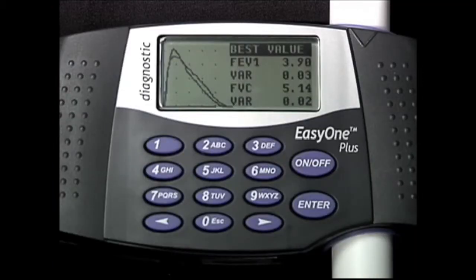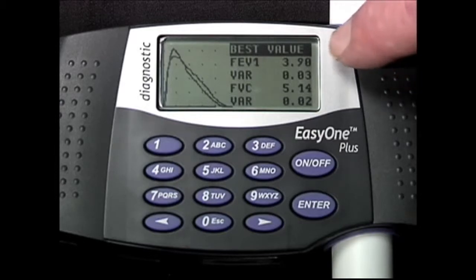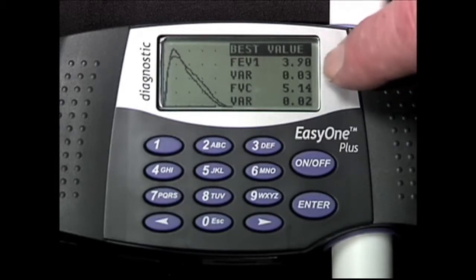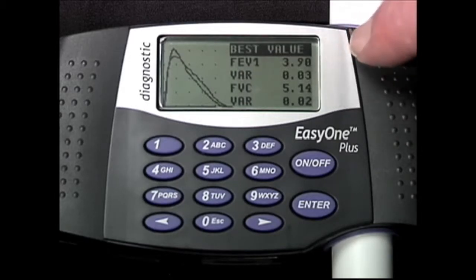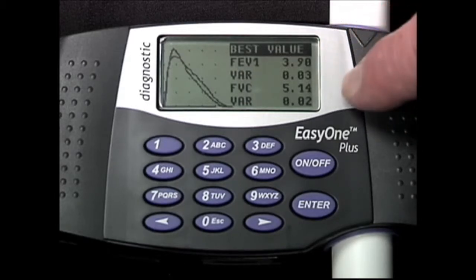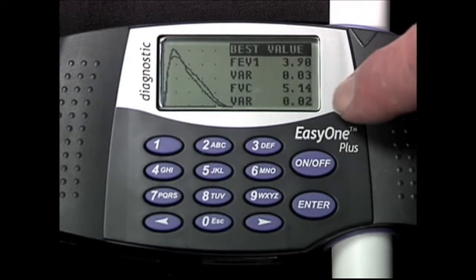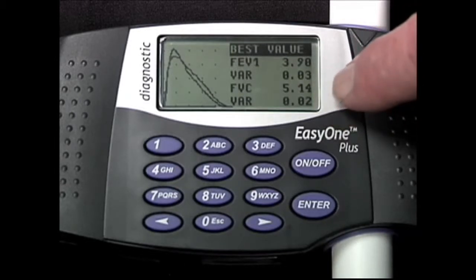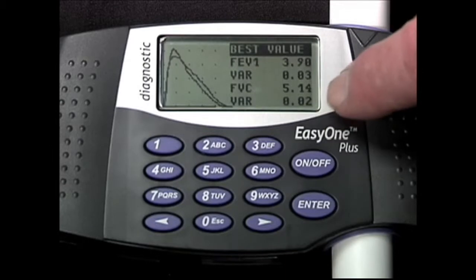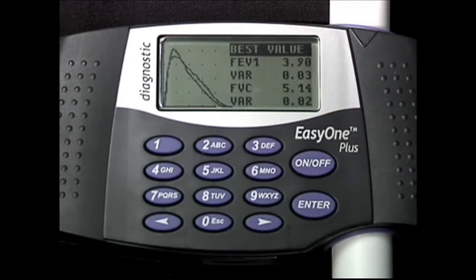Good. Once you have at least 3 acceptable efforts, make sure that you have 2 that match before you can be done with the session. In this case, the FEV1, the 2 best values match within 0.03 liters. That's less than 0.15, which means FEV1 matches. You also need to make sure that the FVC matches within 0.15 liters. This is 0.02. Both of these numbers, FVC variability and FEV1 variability, need to be less than 0.15.